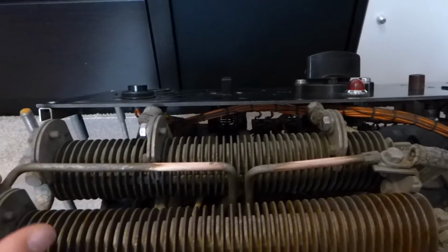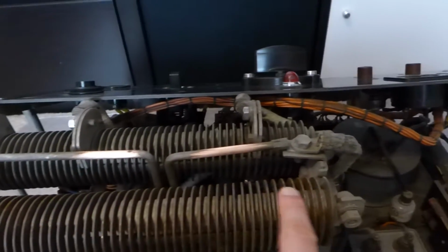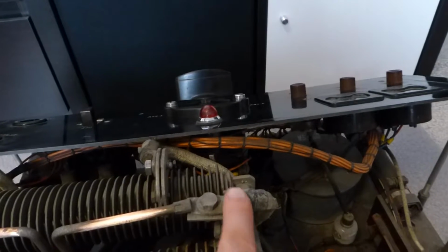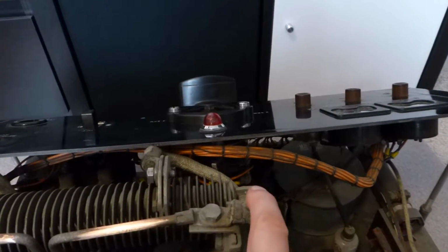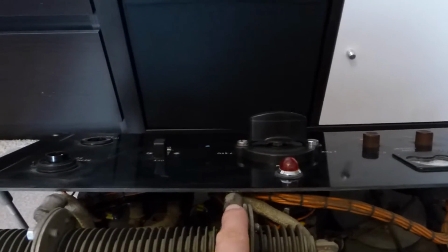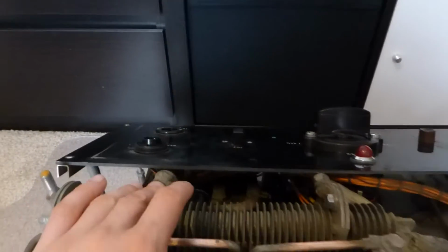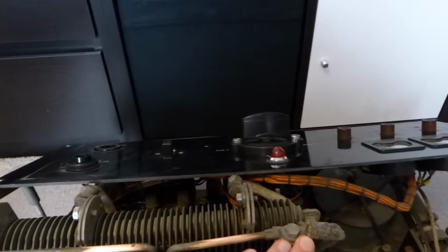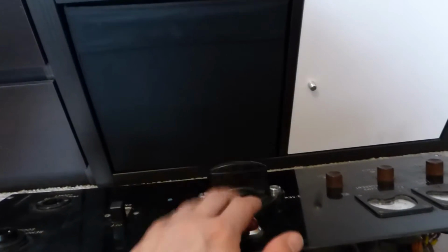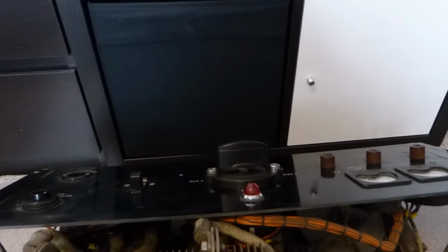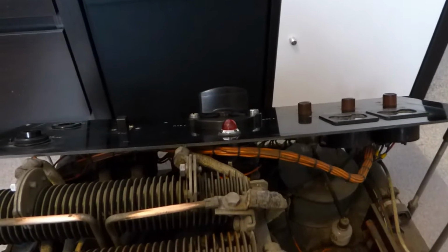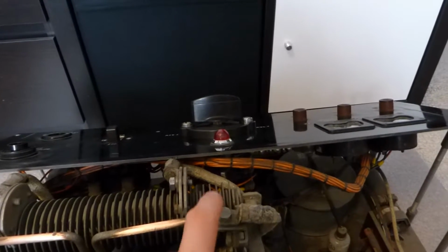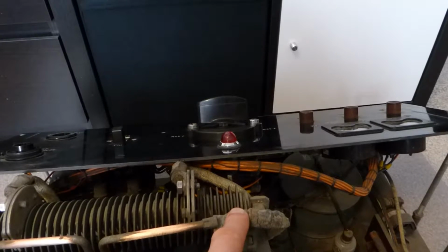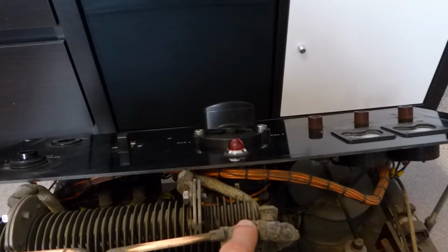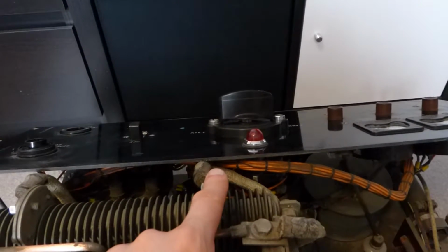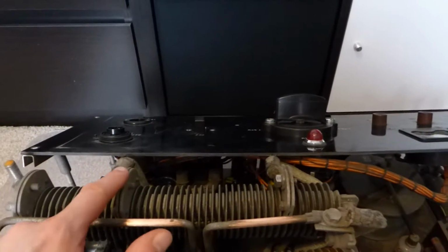So the current comes in here, goes through this first resistor, and then splits off, going down here, through this other bit of resistor down here, and through a bit more resistor down there. These two wires go to the selector switch on the front to select the power. So if you're on the 7.5 kilowatt setting, it taps off the current here. In the 5 kilowatt setting, it taps it off here. And in the 2.5 kilowatt setting, it taps it off here.